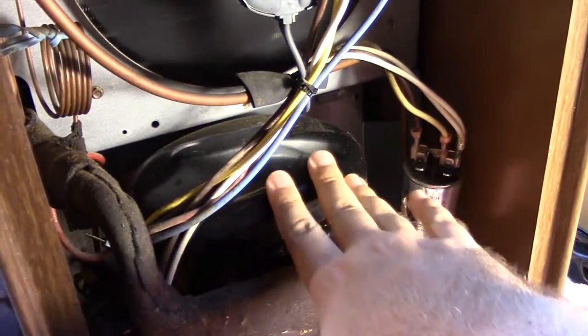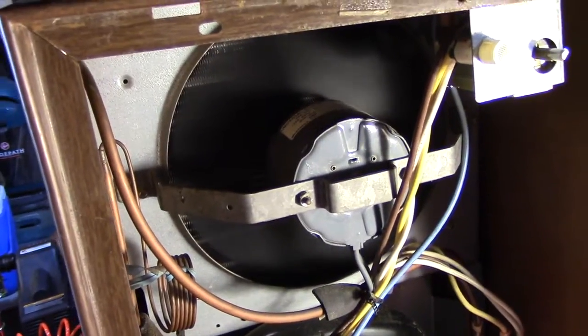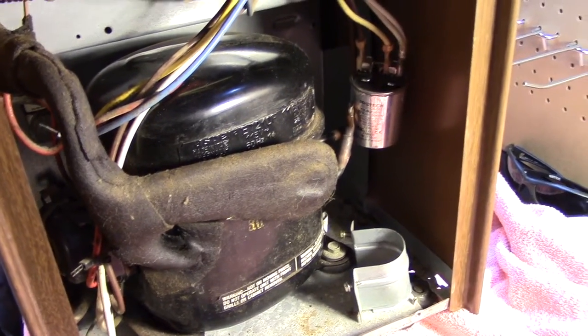The compressor doesn't feel that bad, actually. This is getting warm right now. The fan's picking up speed. The evaporator coils are probably... it's pretty humid today, so they will definitely generate some water. Or condensation, I should say. There's already water condensing on it as it is. A little icy on the bottom, but that'll go away as it runs for a while. Yeah, it's already getting moist.